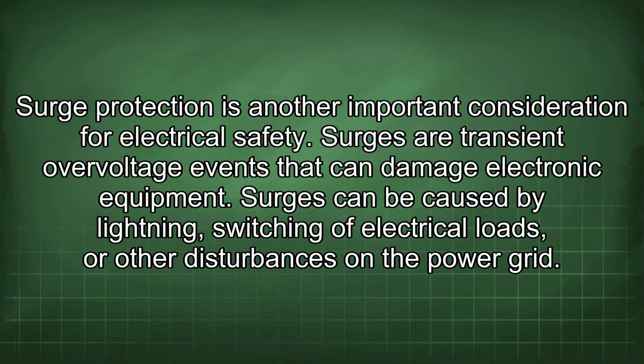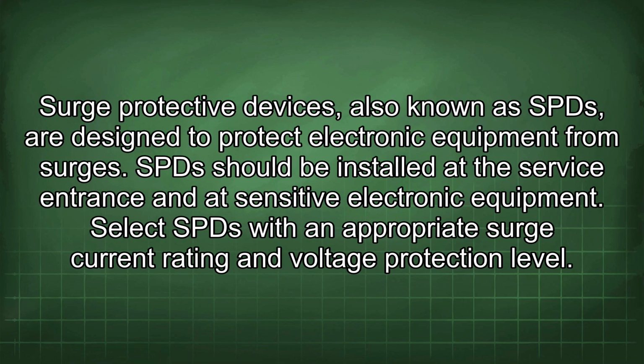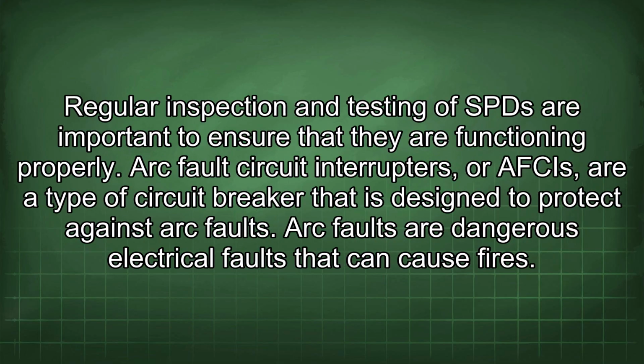Surge protection is another important consideration for electrical safety. Surges are transient overvoltage events that can damage electronic equipment. Surges can be caused by lightning, switching of electrical loads, or other disturbances on the power grid. Surge protective devices, also known as SPD, are designed to protect electronic equipment from surges. SPD should be installed at the service entrance and at sensitive electronic equipment. Select SPD with an appropriate surge current rating and voltage protection level. Regular inspection and testing of SPD are important to ensure that they are functioning properly.